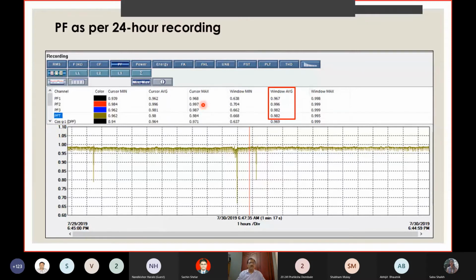This is the same facility, another window. This is the power factor. As you can see here, 0.982 is the average power factor for the day. See, when you talk to Mr. Sachin Shelar, he will tell you what it means to read data downloaded from the software of a meter. So here, the cursor is the point at which I have kept the red line. Window is the entire window. This is a 1-day window, as you can read here at the bottom. This is a 24 hours window.